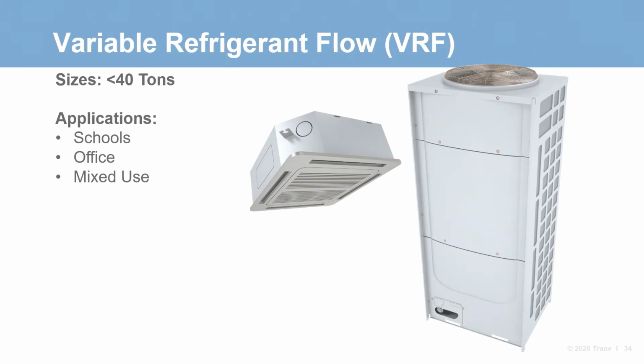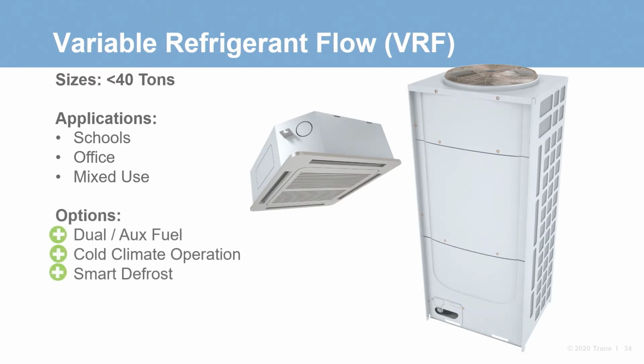The flexibility of these systems, with refrigerant pipes running through the building instead of ductwork, makes them a good candidate for a wide variety of applications. VRF also offers a lot of capability in terms of operation. Auxiliary fuel is possible with electric terminal heat, and most VRF manufacturers offer cold climate capability with heating operation well below 0 degrees. Another great feature within most VRF products is smart defrost control.